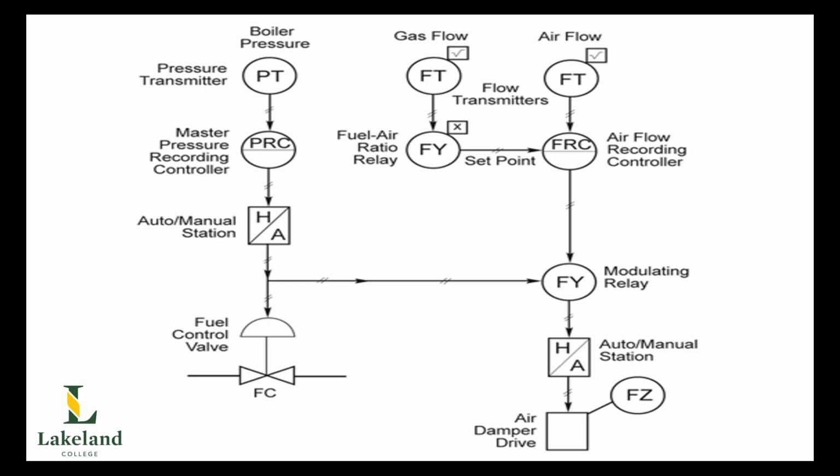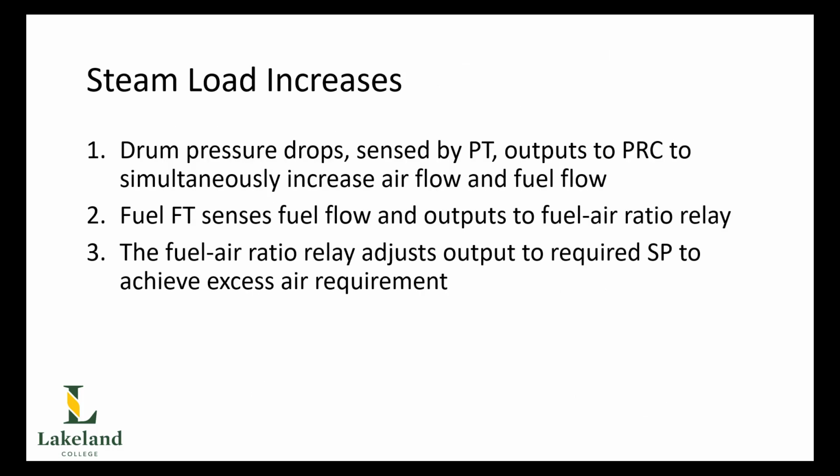Okay, so now that we've gone through the main overview of it, let's take a look at it now with a couple of scenarios while you keep figure 10 open in front of you in your textbook, and you can be referring to this diagram while we discuss it. Okay, so here's how we can summarize a steam load increase and what happens. So first of all, when the steam demand upon the boiler increases, its drum pressure is going to drop.